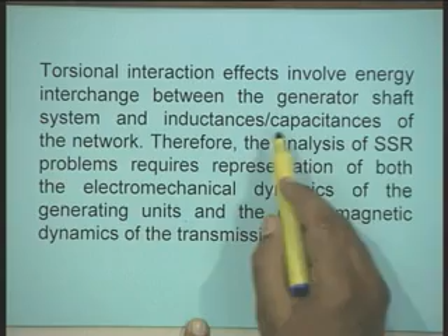Another very important aspect is that the torsional interactions involve energy interchange between the generator shaft system and the inductances and capacitances of the network. Basically there is an exchange of energy between the generator shaft system and the network inductance and capacitance, because they are the energy storing devices. Therefore, the analysis of the SSR problem requires representation of both the electromechanical dynamics of the generating units and the electromagnetic dynamics of the transmission network.